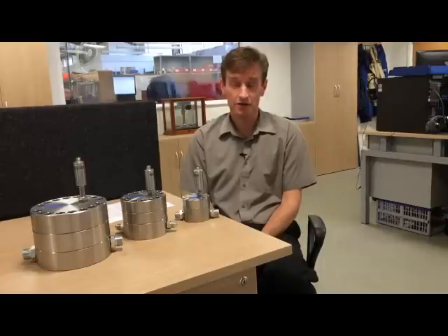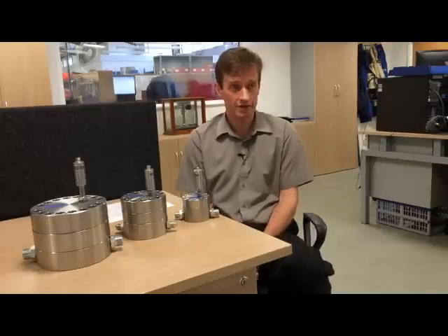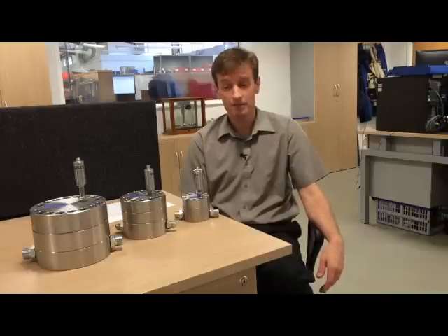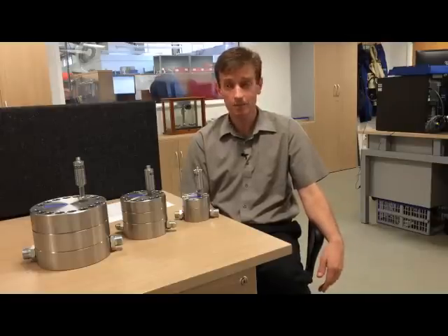The accuracy of these meters is significantly better than the average turbine meter, and we are aiming for a meter accuracy in each device of 0.5 percent of indicated reading. And the transducers you see on the top of these, they incorporate a microprocessor which corrects or linearizes the flow to give you a linear output relative to the oil flow.